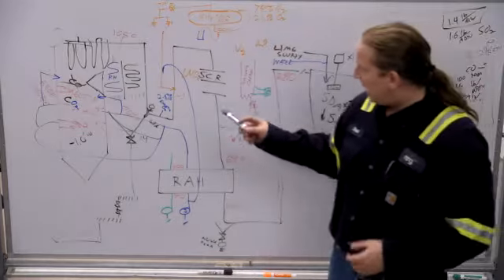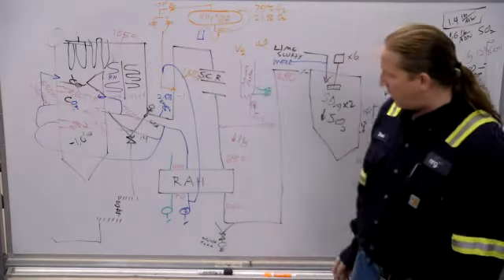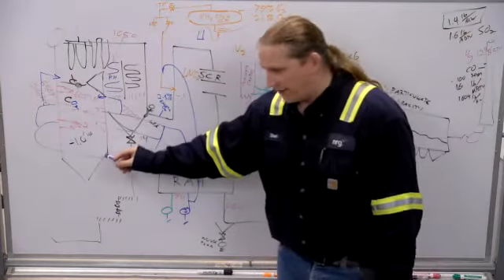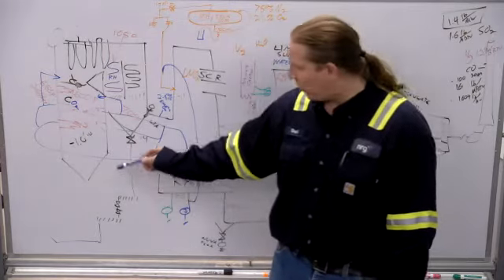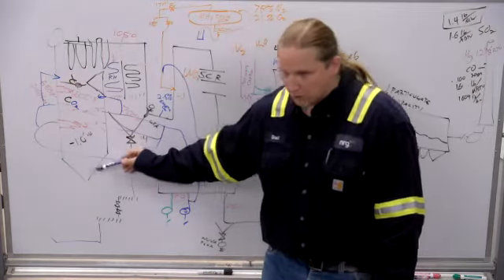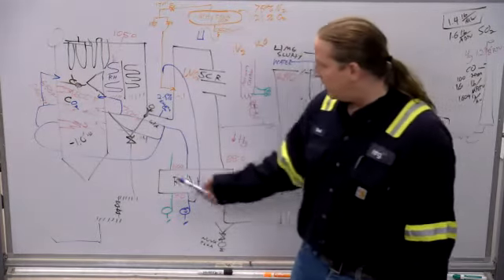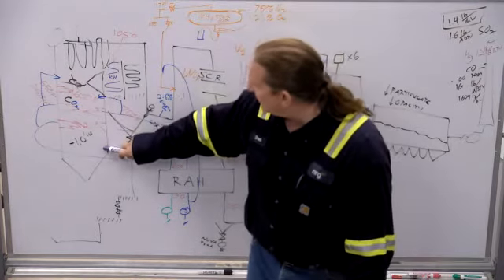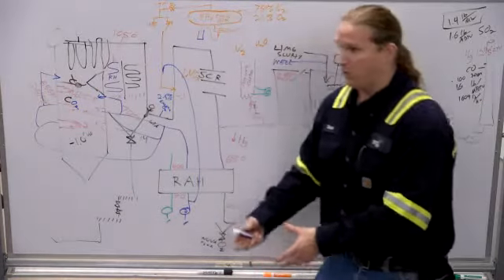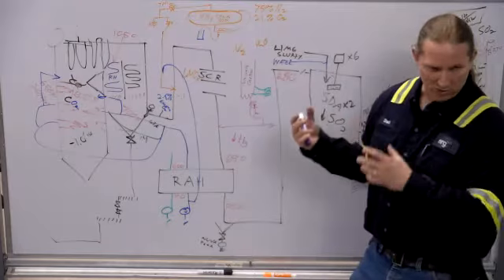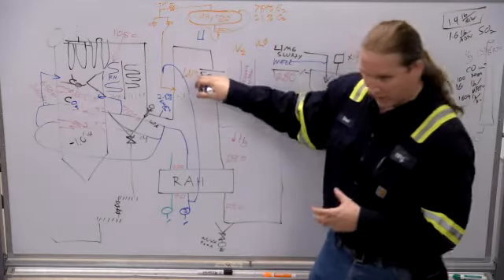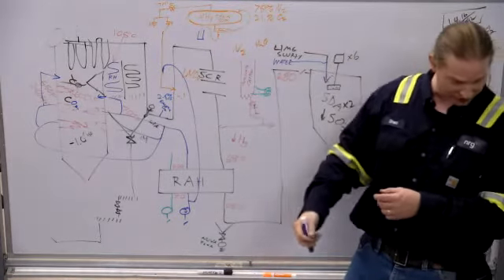Now the times that that happened really bad was when we were dealing with water wall leaks and then the water's blowing out in that corner at the slope. And it used to be doing it on the one corner over and over again. And then that swath of flue gas on the north side by the corner had a hell of a lot more moisture in it. And that made the ash block up in those little pencil sized holes.